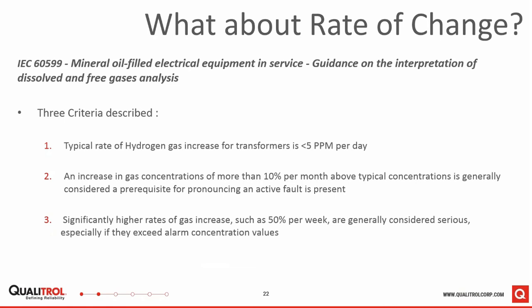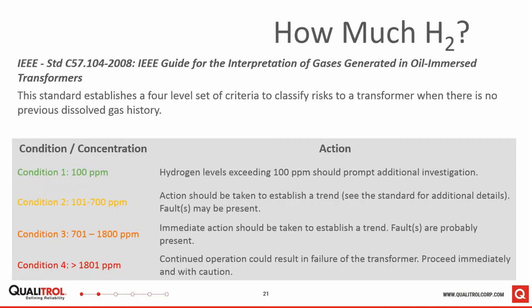Prior one. Oh, there we go. So for those that have actually read IEEE standard C57.104, it is interesting to note that these guidelines were published, and it talks about in the guide that these are for large power transformers, which of course typical network transformers are not going to be considered large power transformers.